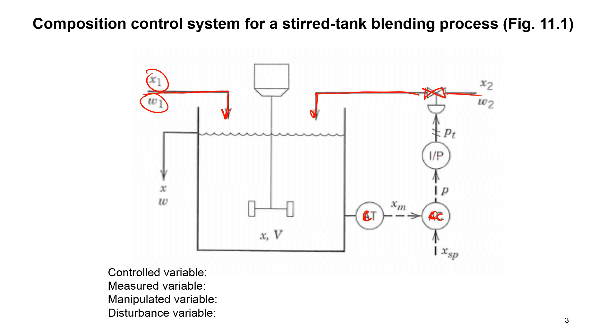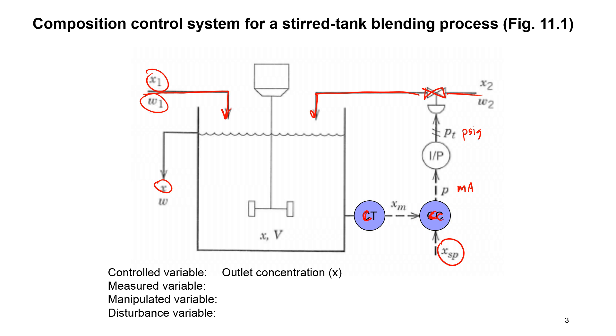We have an I-to-P converter. This is going to be coming from our controller — that might be a milliamp signal coming from our controller, and that might be a PSIG in the case of a pneumatically controlled valve. We have our set point. For our controlled variable, in this case, we're going to have the outlet concentration of our tank — that's X coming out of the tank. Our measured variable is also the same, assuming a well-mixed reactor where outlet concentration equals the concentration inside.